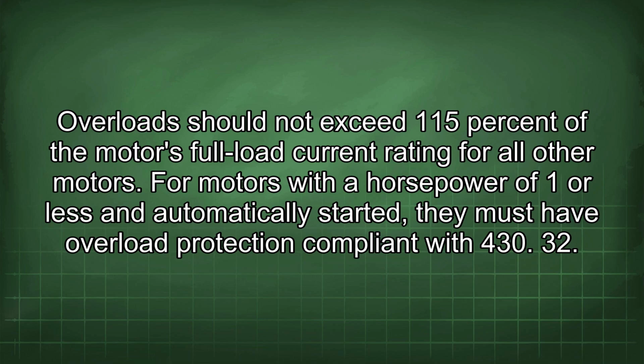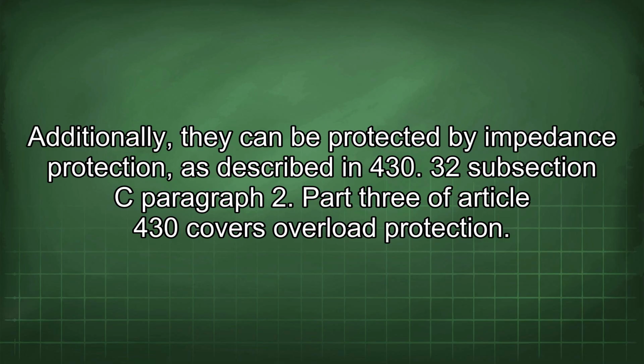For motors with a horsepower of 1 or less and automatically started, they must have overload protection compliant with 430.32. Additionally, they can be protected by impedance protection as described in 430.32 subsection C paragraph 2. Part 3 of Article 430 covers overload protection.